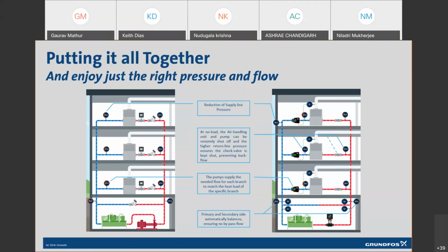We also see that your pumps are connected with the BMS. So if you have a condition where there is no load, you can switch off the AHU and the pump remotely. And that makes it a system which adapts itself and communicates with the management system. The pump supplies the needed flow for each branch to match the heat load of that specific branch, which we have discussed. And here you see the primary side automatically balances, ensuring no bypass flow at any point of time. Because if there is a bypass flow, the temperatures will vary and the pump will take action accordingly.